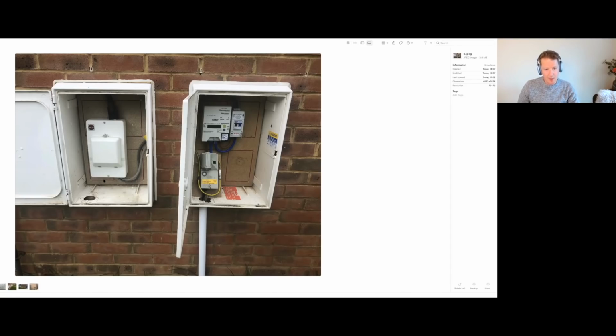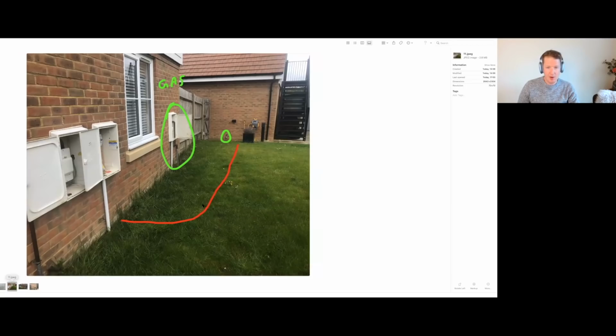So then from here, what we would have to do is run the cable out. It'd have to be an armored cable, because it's going to have to be buried in the ground. So the customer, again, amazing. They've produced this wonderful picture with markings. So we've got the gas meter here. That's the gas pipe going into the garage. And we can see the route here. We could run a cable down and then a trench in the ground into the garage.